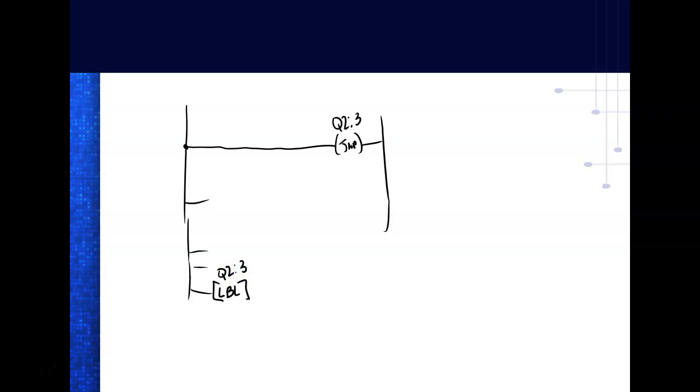Why would we use this? Because it would always skip over all these rungs and go down to there, right? You understand? With no input. As soon as I put an input into that rung, this is conditional. So now we're saying that contact has to be closed before the jump occurs. So conditions have to be met. So like I said, very seldom do we use an unconditional jump instruction unless we're troubleshooting, right? And we want to skip over a section of a program on purpose, then we could use a jump.